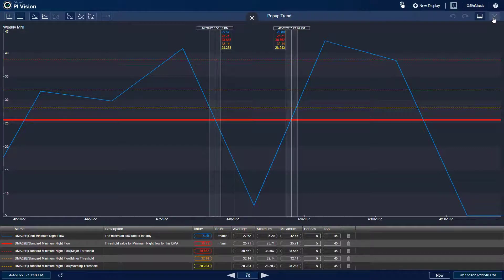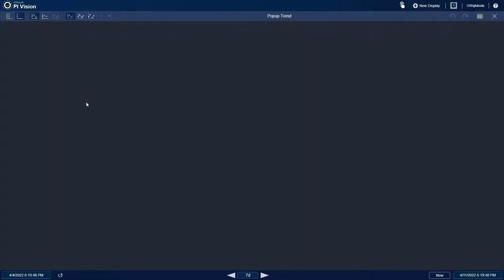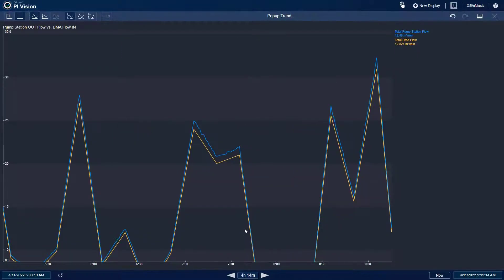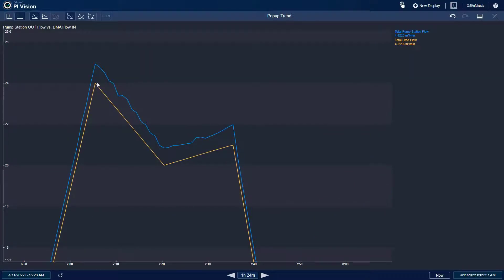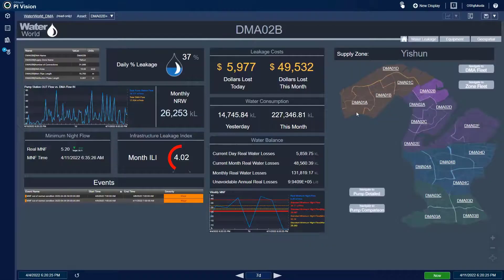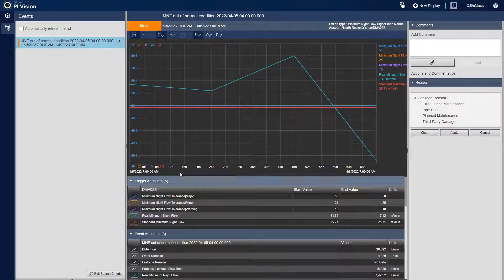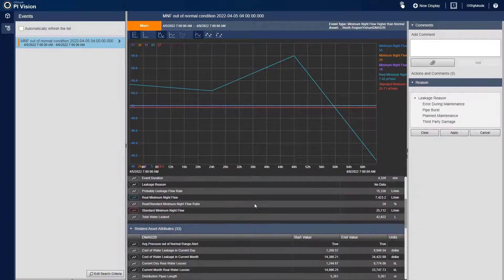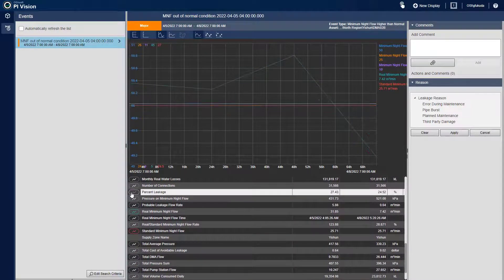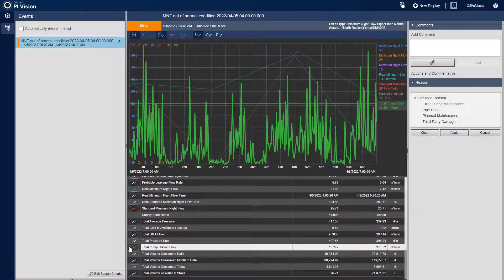The engineer uses trend cursors to mark exactly when the MNF alert threshold was exceeded, then checks the water balance over the past day. They view a real-time trend of total water flow pumped compared to the sum of all flow meter readings — if total flow pumped is much higher than the flow meter sum, there is a potential leak inside the DMA. The engineer consults the event list for this DMA, views details of the first major leak event, then brings on an operator to inspect the potential leak via a shared link.